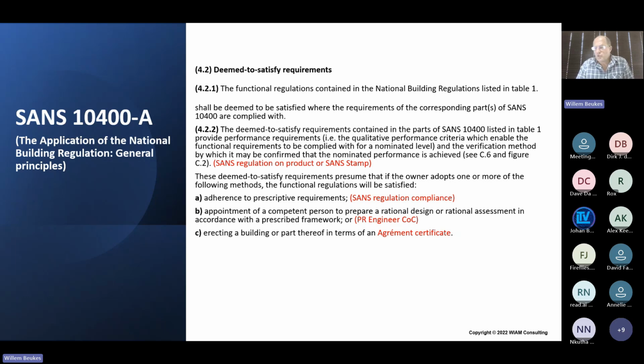If you don't have either of those two levels of certification for any product you use in the existing occupation, our regulation states that you need a rational design from a competent person, a professional engineer - in this case a structural engineer or fire engineer - to provide a rational design to use that product in the existing occupation. That's the starting point in the South African regulation, to make sure that whatever product you use as a fixed installation, meaning it cannot be moved, it's not a portable item, you need to comply with these regulations. Unfortunately we are currently at a level where you need a rational design from a professional engineer to ensure structural stability and fire compliance are met for any installation.